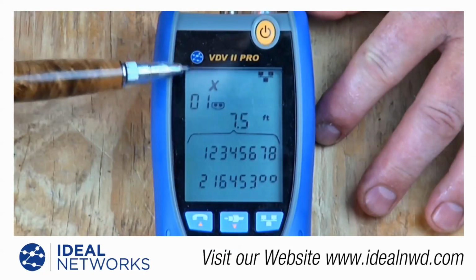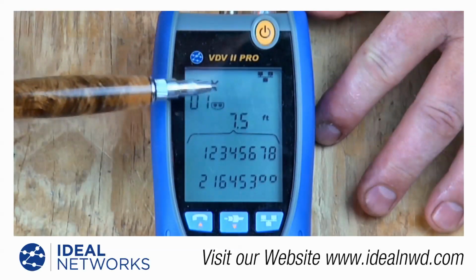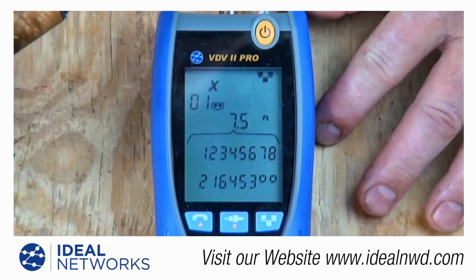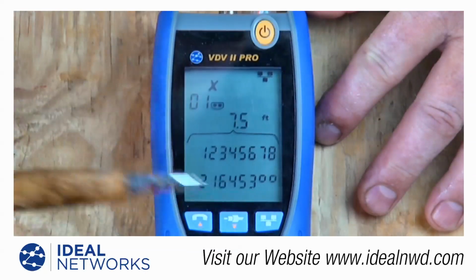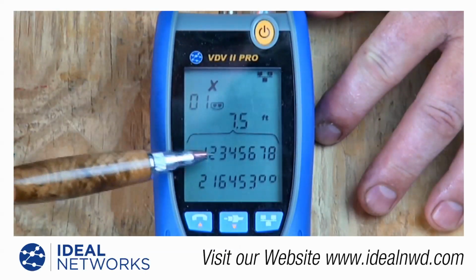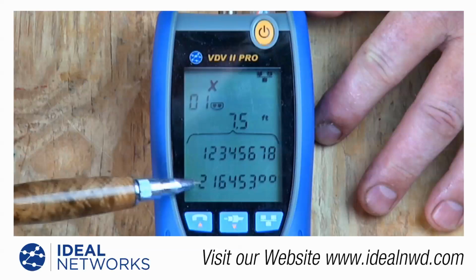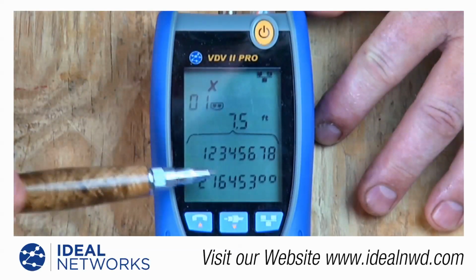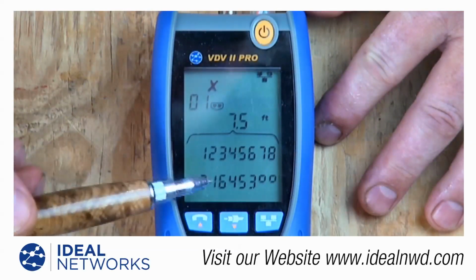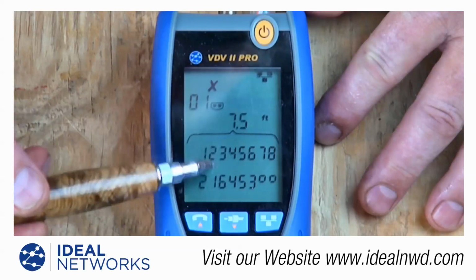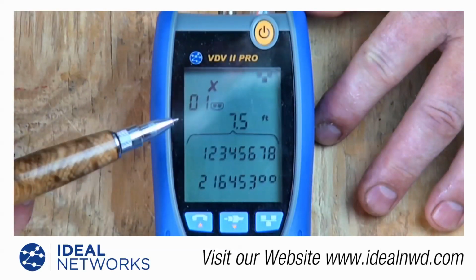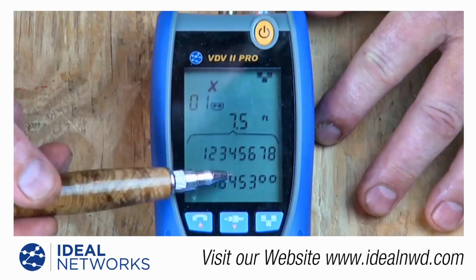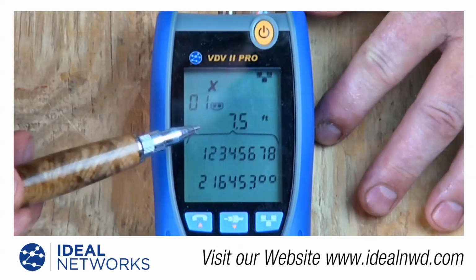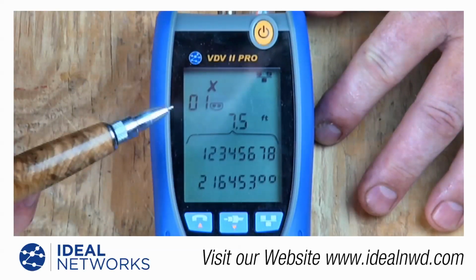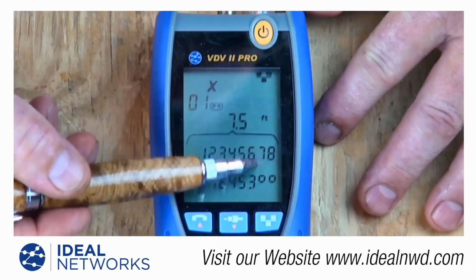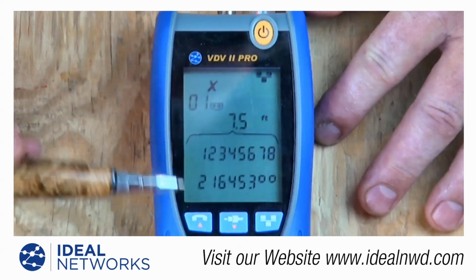It's still seeing the first remote out there like we'd expect, and it still sees a cable about 7.5 feet long, but now we have multiple errors. The top row should be 1 through 8, but the bottom row says 2, 1, so there's that reversal we saw on the first cable. You'll also see 3 and 6 are reversed, so there's a reversal in the green pair. It likes 4 and 5, they're the same top and bottom, so that pair, the blue pair, is okay. And over here, it sees an open in pins 7 and 8.